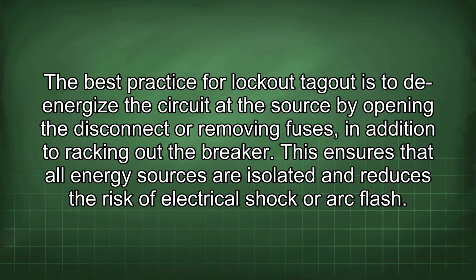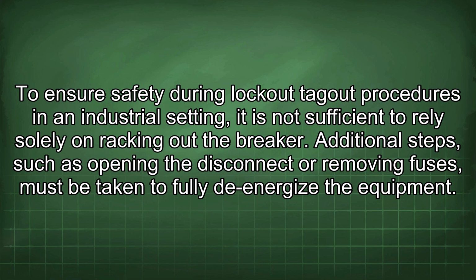The best practice for lockout tagout is to de-energize the circuit at the source by opening the disconnect or removing fuses, in addition to racking out the breaker. This ensures that all energy sources are isolated and reduces the risk of electrical shock or arc flash. To ensure safety during lockout tagout procedures in an industrial setting, it is not sufficient to rely solely on racking out the breaker. Additional steps, such as opening the disconnect or removing fuses, must be taken to fully de-energize the equipment.